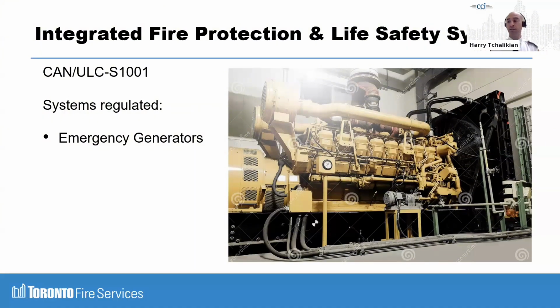Your generator company could do this with a load bank, meaning they plug in a load bank, which is like a technical term for how conventional stoves work. It's a heating element that draws the rated power and current, and that would be a pass. Now with the CAN/ULC-S1001, that full rated capacity has to actually come from the emergency power systems that it's giving electricity to. So you actually have to run everything that receives emergency power. So your elevators, your fire pumps, your lighting, all of that has to happen. It's not once per year. It's going to be every 5 years. I'll get to the frequency, but this will take a higher level of coordination. So just be aware that once every 5 years, whatever your annual is, that once-every-5-year test has to be at a much higher level to confirm all the integrations.